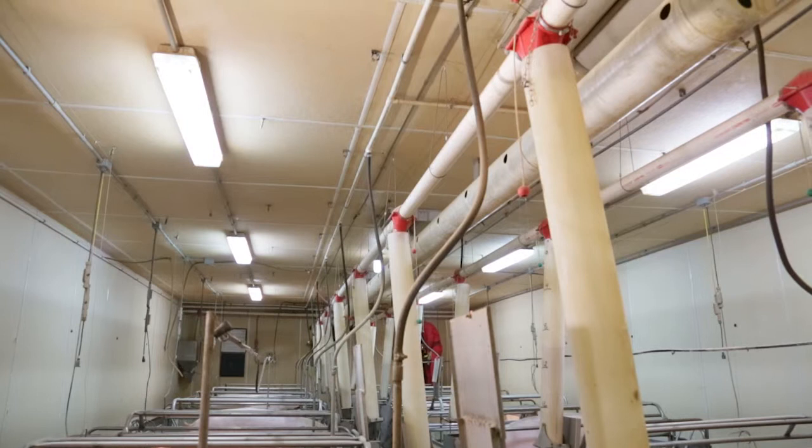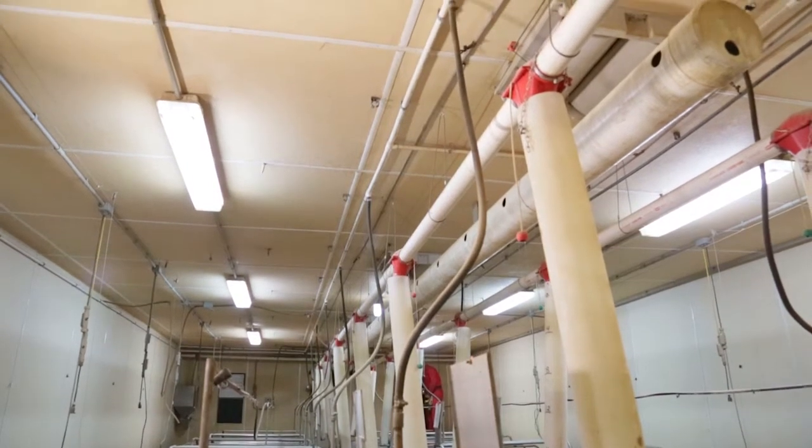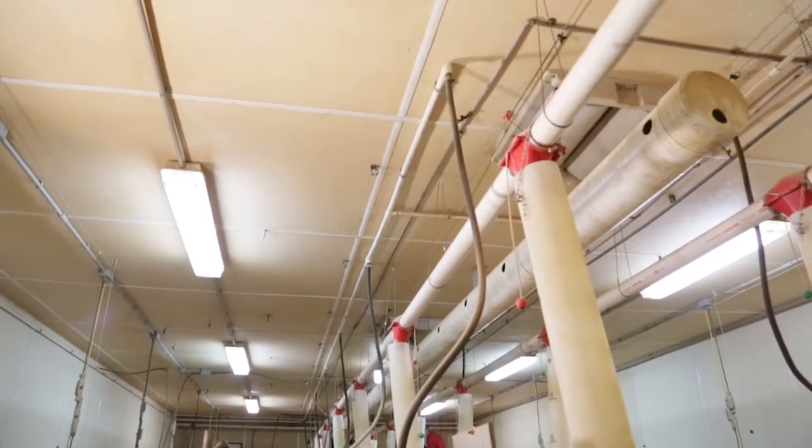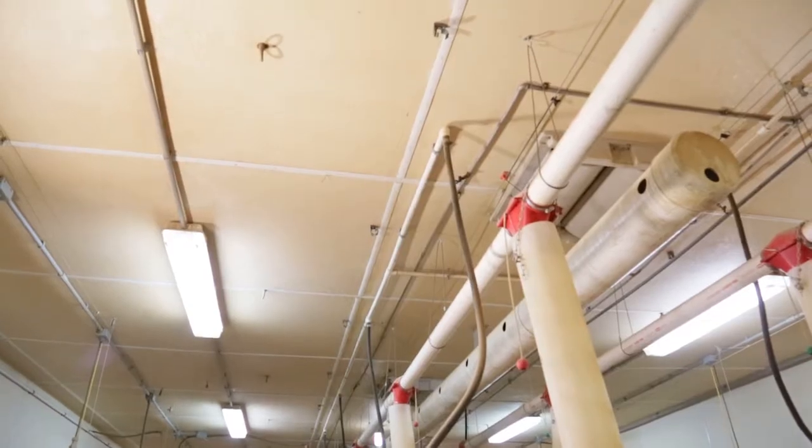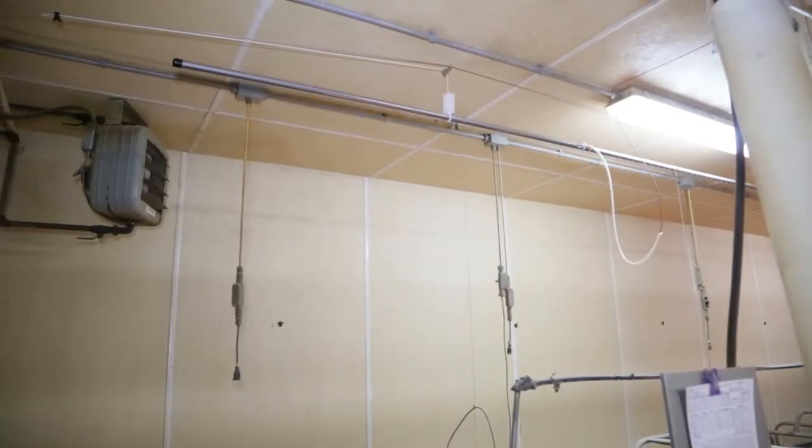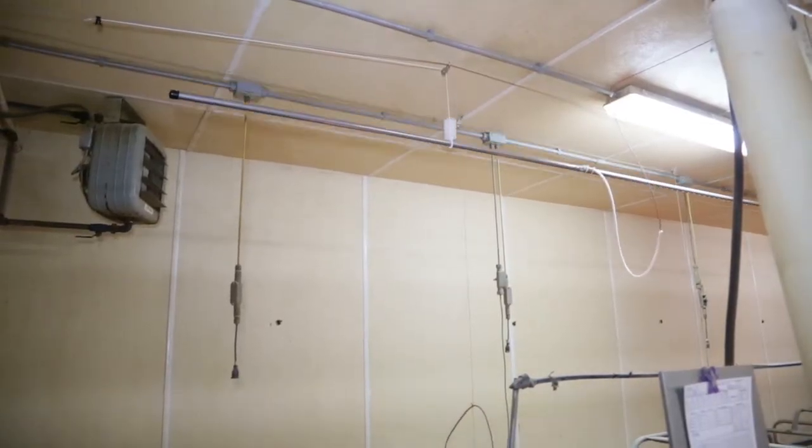Look for obstacles such as ceiling vents, lights, feed lines, etc. that will prevent the corona pipe from rising up and out of the way of the workers. A fully lifted corona pipe will be 8.5 to 9.5 inches below the ceiling.